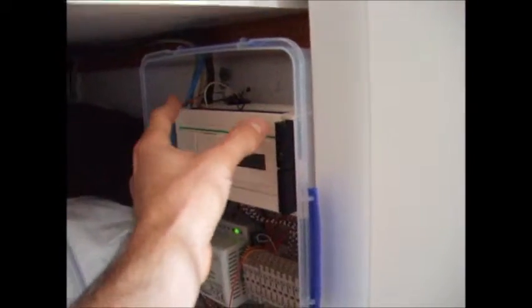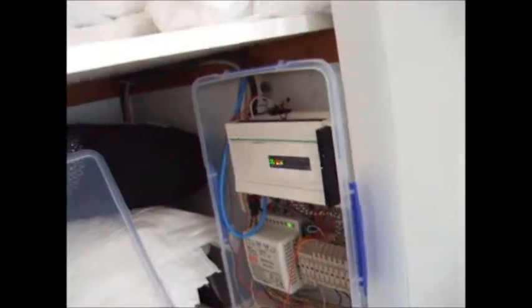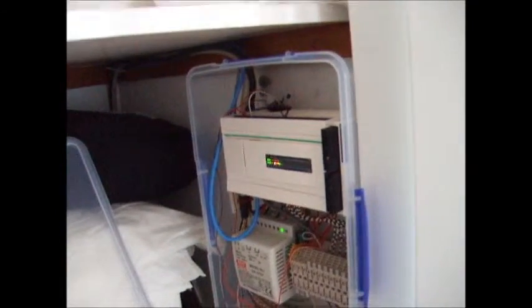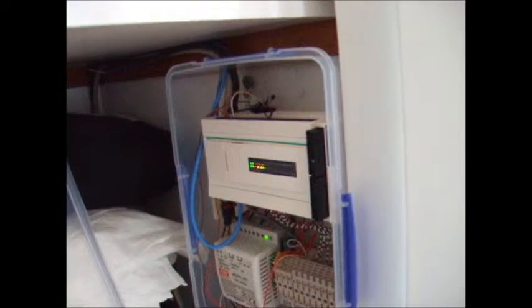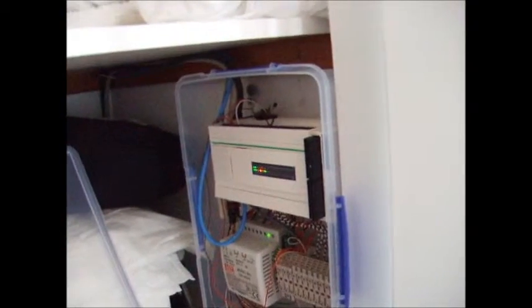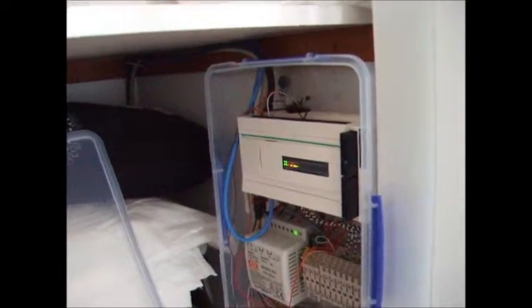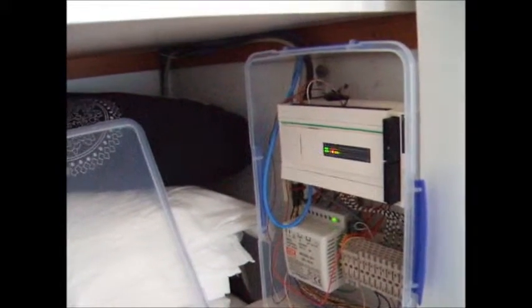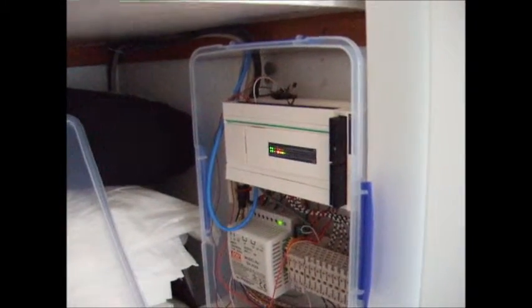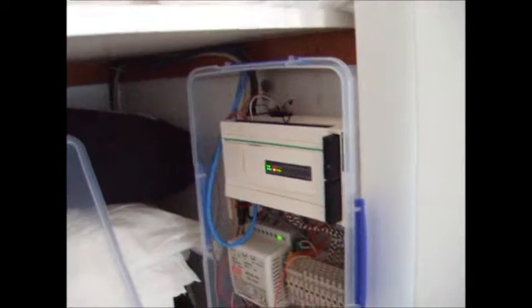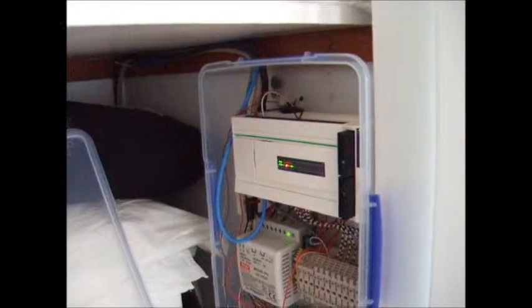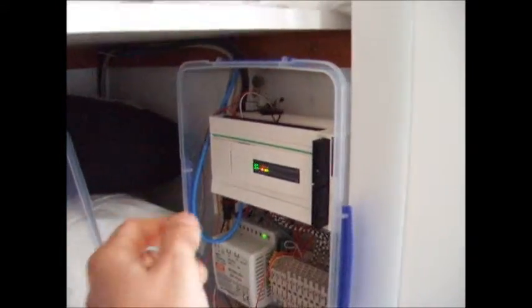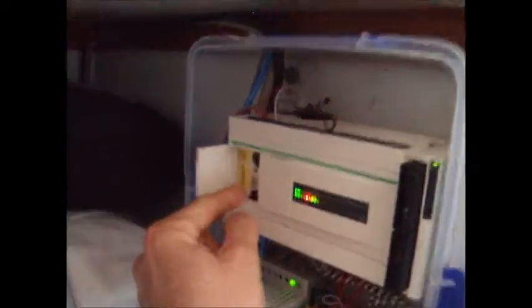Secondly, you need a real-time clock. In other words, you need a chip or a device inside the PLC that can actually store and remember time and keep time. And you can set that to normal time, and therefore you can read that value and you can compare it to a set point. In other words, a start time or an end time when you do programming. Without a real-time clock, you can't really do that. You can only have time delays, time on, time off, etc. So that comes as a module that can either clip into a modular PLC, goes in a little spot here, or it comes built in like this one has.